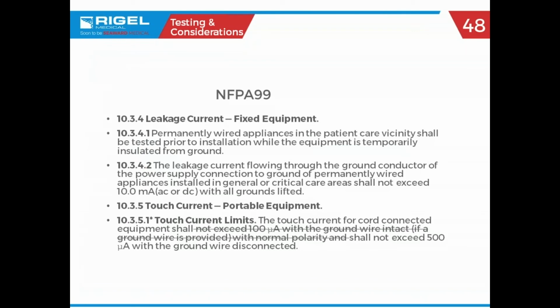Leakage current, fixed equipment, portable equipment. We already kind of talked about fixed equipment, right? And again, fixed equipment hardwired into the voltage of the facility, OR lights, your CAT scanners, 10 milliamps. Touch current limits, and this again goes back to that change that we only have to test in single fault conditions, because allowable leakage current is higher in single fault condition.